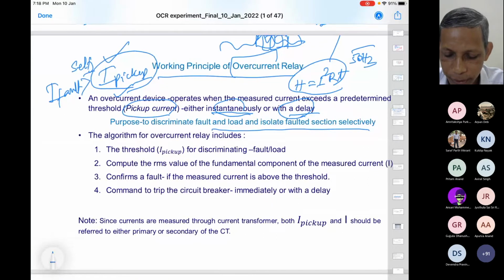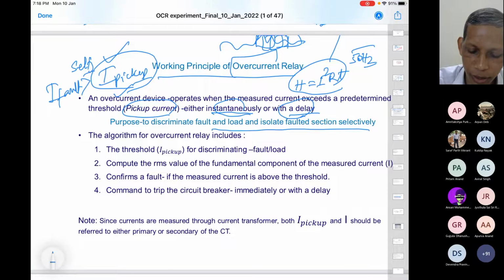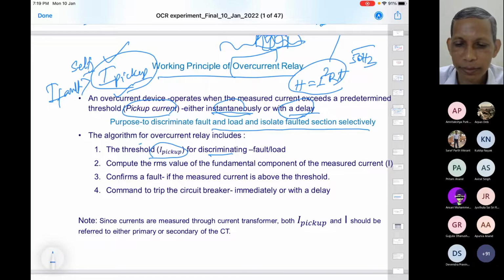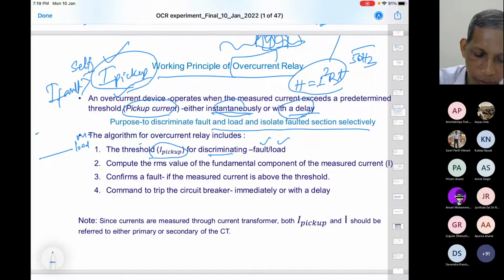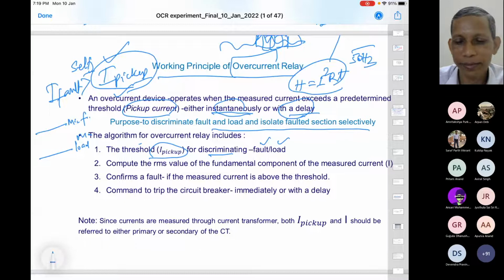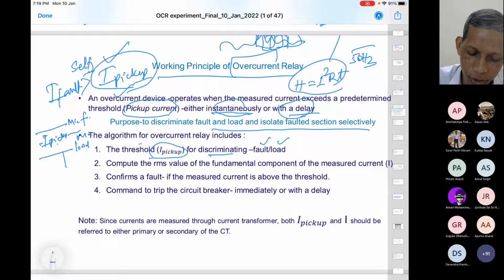Fine, so we'll proceed. Now, the algorithm for the overcurrent relay includes a threshold pickup, which is a discriminating point for fault versus load discrimination: overcurrent, load versus fault. I can put here the maximum load level, and this is the minimum fault current level. So in between we set a pickup, so that when the current crosses the pickup, we declare a fault.